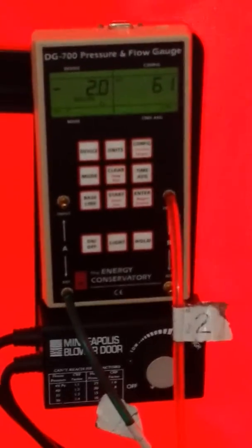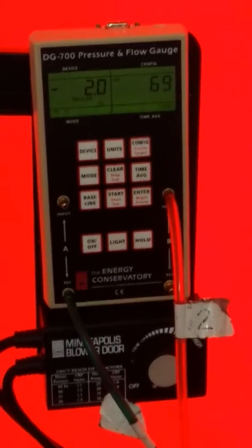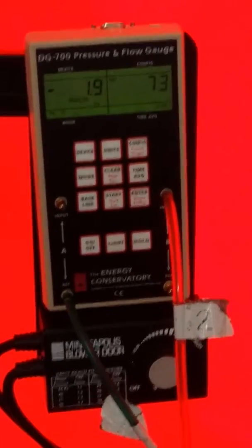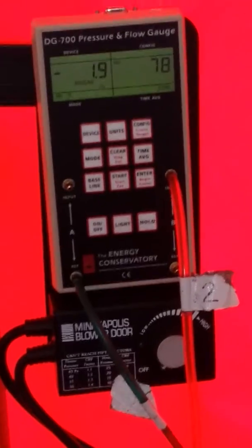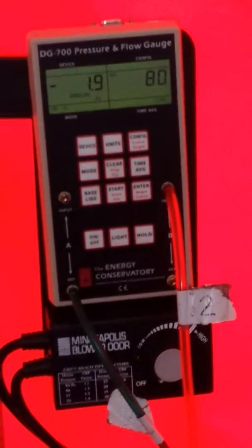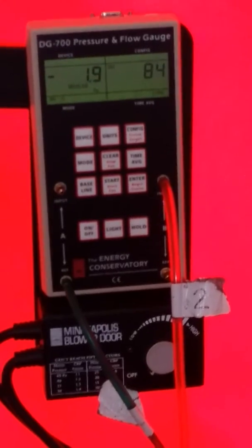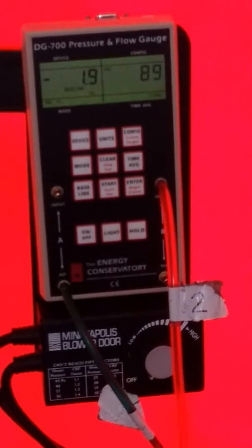It's like you were saying, so you don't even have to remember. Yeah, because otherwise I'd have to aim for -52 one day and -47 another day, and I'd be trying to do that all manually. I just want to aim for 50. So I'll have the manometer help me find my target by resetting my initial pressure. I'm getting rid of that baseline pressure, basically. Then once it gets up there, Tim, are we going pressure flow at 50? What's our mode right now, Eric?